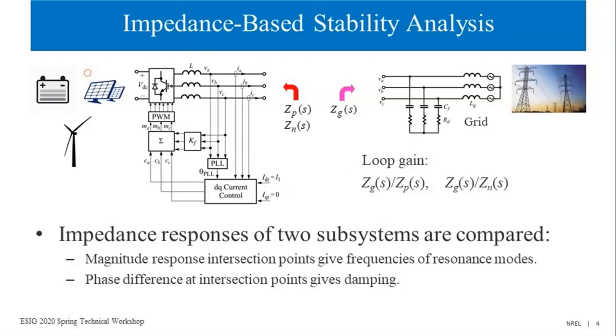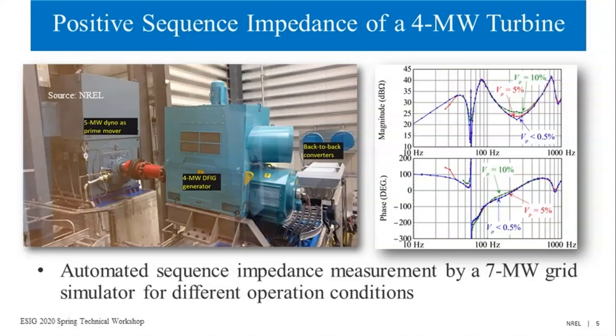But ultimately, the idea is to look at these inverter-based resources and the grid from outside and take a black box kind of approach, mainly because most of the times we don't have good dynamic models covering all control functions. And even if we have them, they are so complex that it is hard to do any kind of analysis on them through traditional methods. So this slide shows one impedance measurement example we did at NREL. It shows a positive sequence impedance response of a 4 megawatt wind turbine. And this kind of response can be used not just for stability, but for model validation as well, basically evaluating a model at different frequency ranges.